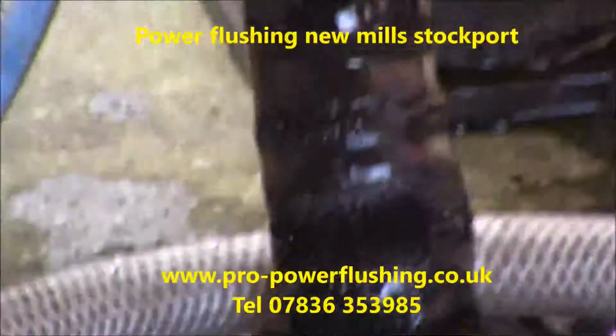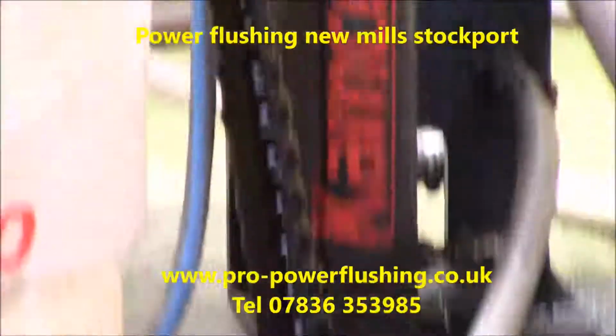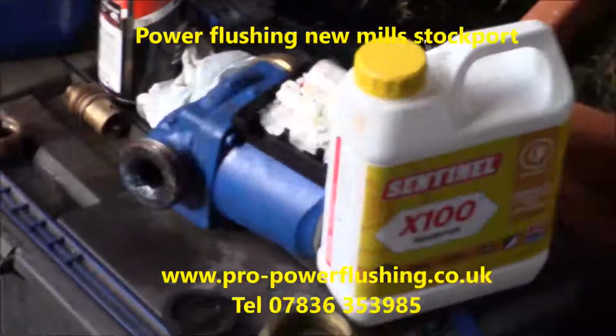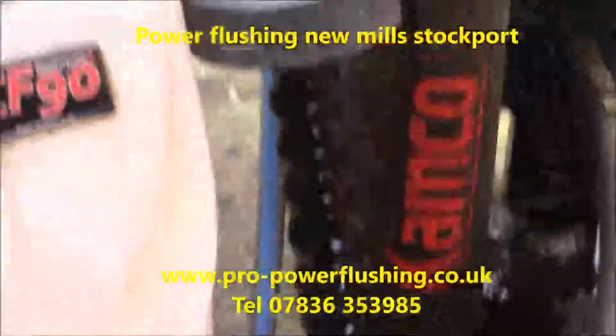So that's what we've taken out of the central heating system today. That's what is blocking the pipe up, which we showed you at the very start of the job. And this is what is in the pipework, radiators and boiler at the end of the day. We've cleaned the pump up as best as we can. Pump's quite old, but it still seems to be working. We're going to make a note though that possibly the pump needs changing at some stage. Okay, we're just going to get on with the job. We'll get back to you later.